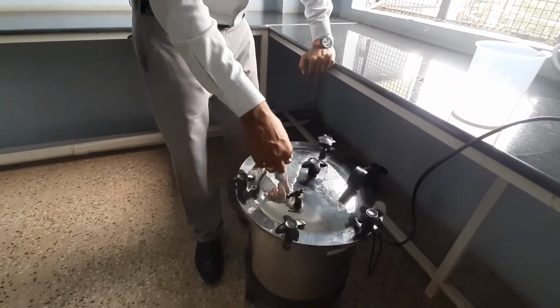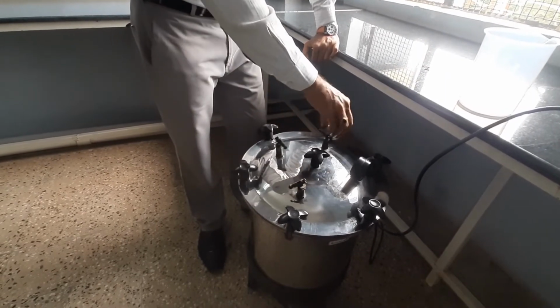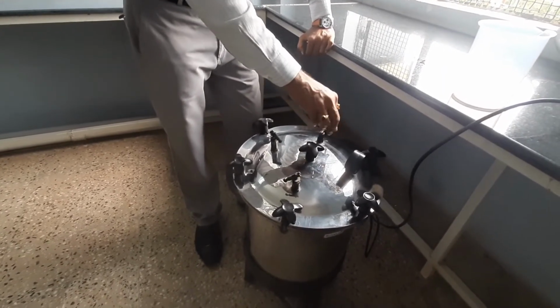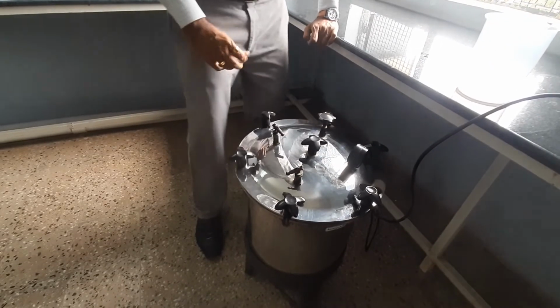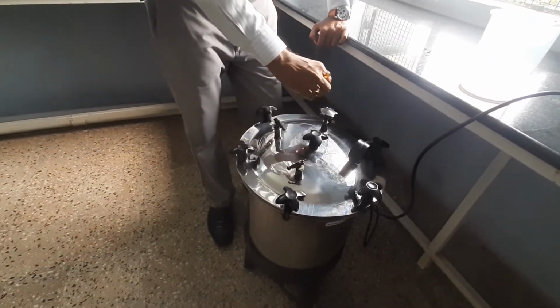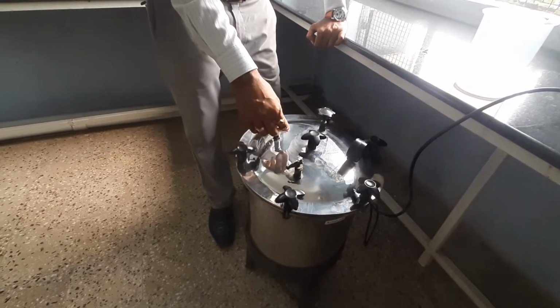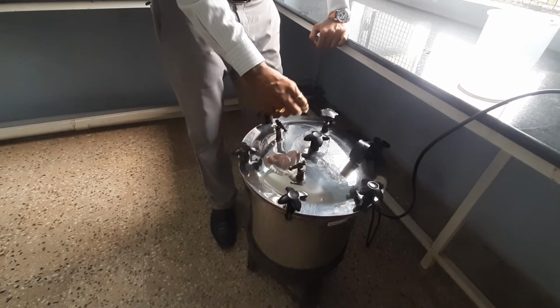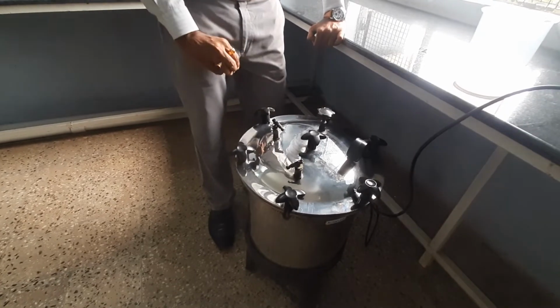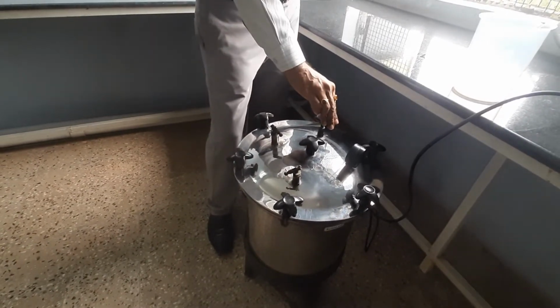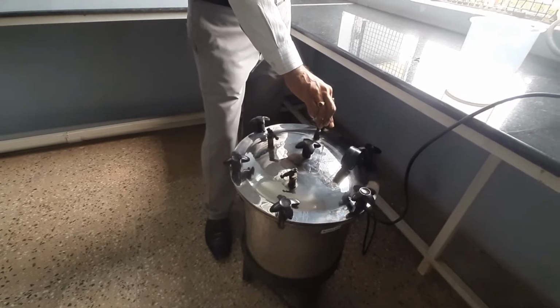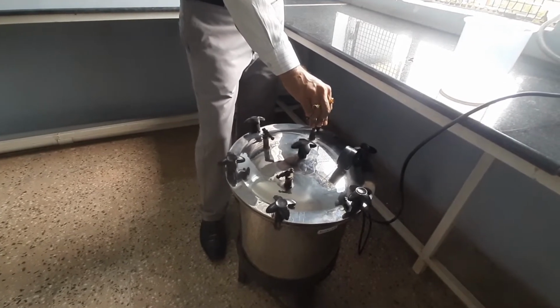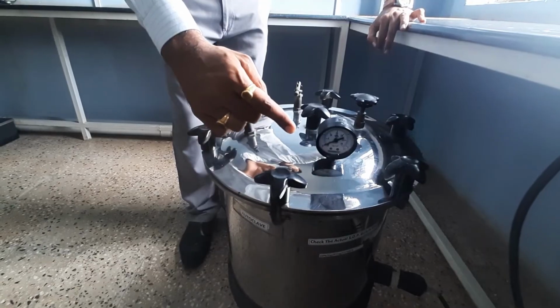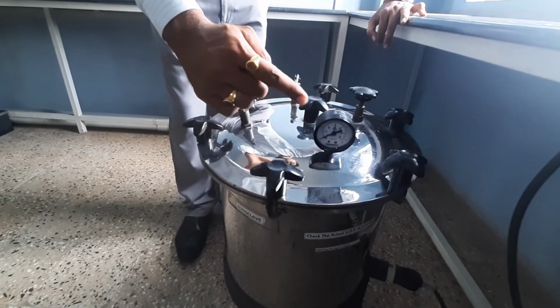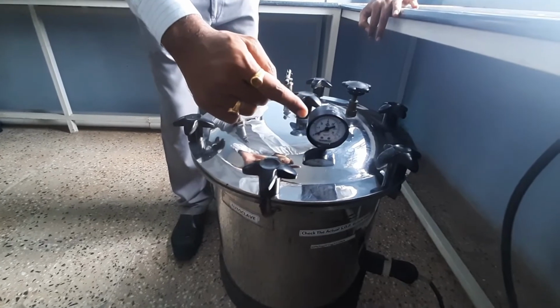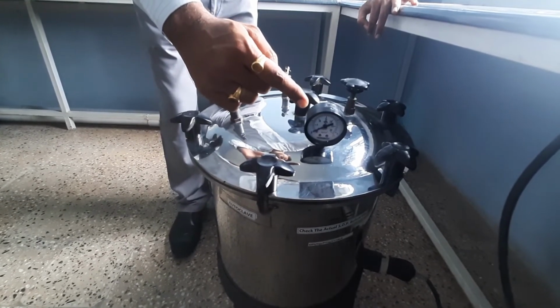Vent is open. Then, when the vent is open, the safety valve is set to the required pressure. When steam comes out for 5 minutes, then close the vent and the steam pressure starts rising, and it should be maintained at the required level. Pressure starts rising, it is shown in this pressure gauge. It should be maintained at the required level.